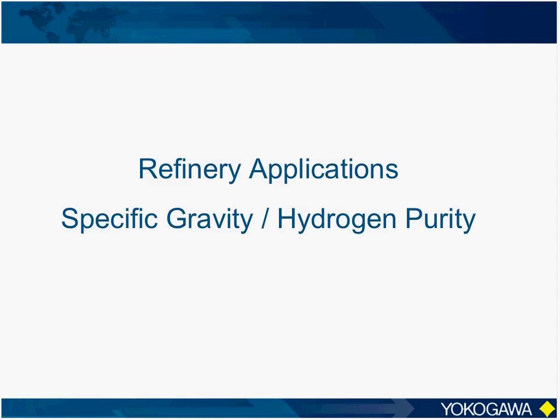Next, we're going to discuss some applications for the vibrating element system found in refineries. These are typically specific gravity applications, but in some cases, hydrogen purity can be calculated. The applications where hydrogen purity can be calculated are typically multi-component streams that act as a pseudo-binary gas stream. In these cases, as the hydrogen concentration increases or decreases, the concentration of the other components increases or decreases at the same rate. And that means the density of the background gas can be calculated and treated as a second gas in a binary system.